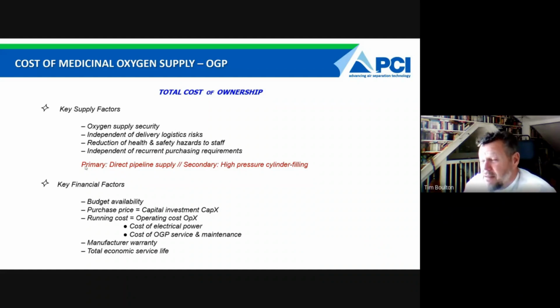They are maintenance intensive, so they need to be serviced after 2, 3, 4,000 hours. And their economic service life on a typical oxygen high pressure booster will be around, I would say, about 15 to 20,000 hours. So if you were to use those 24/7, then really at the end of about 3 years, you'll be needing a new high pressure booster. The alternative is to put your oxygen generation plant as close as you can to your major users, either operating theaters, ICUs, emergency rooms. If you can get your oxygen generation plant quite close, it is very, very cheap and easy to lay a rudimentary pipeline.